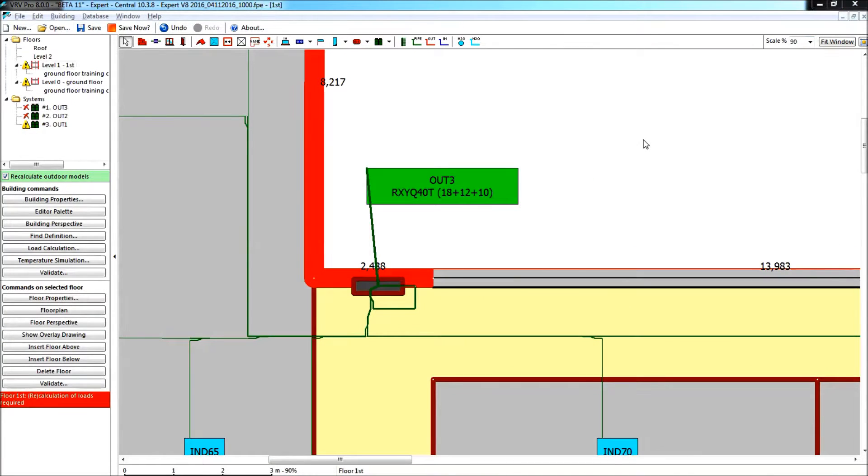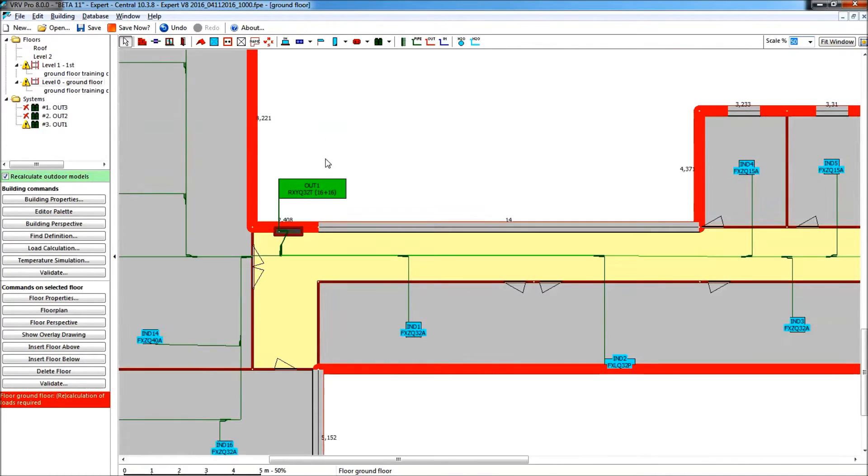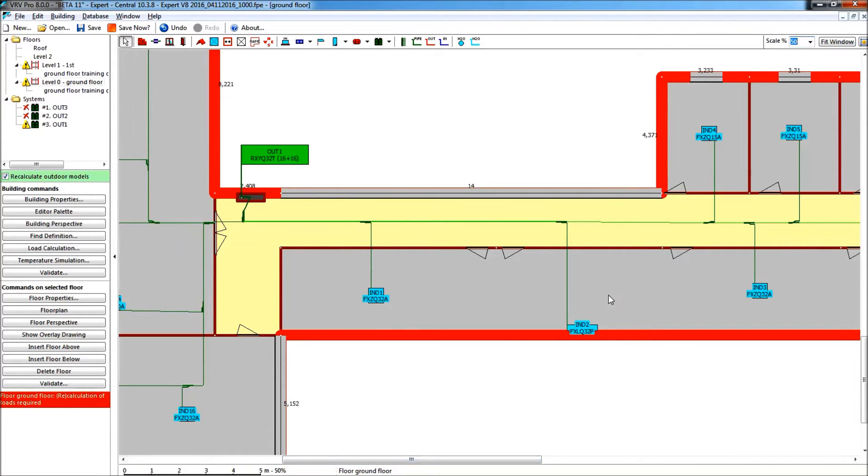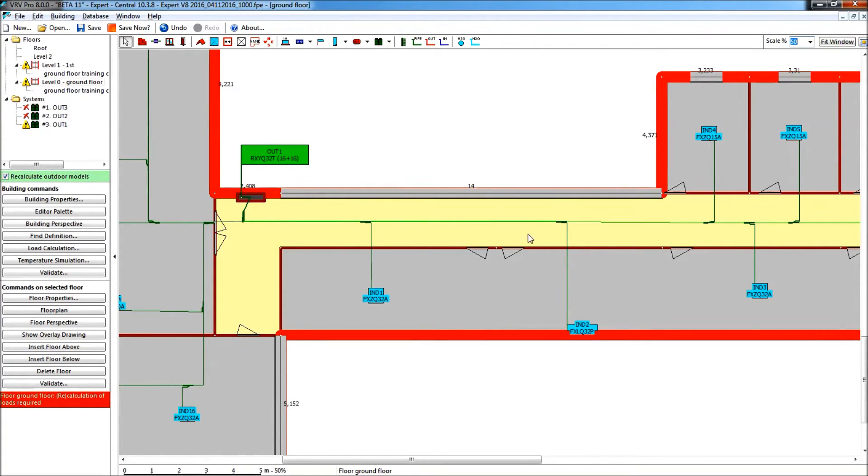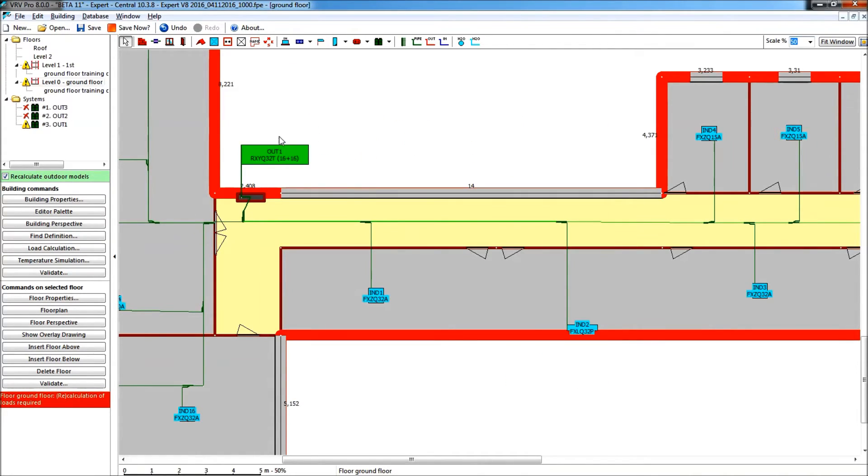There is an aspect that I forgot to mention to you, but just before we leave, I have to go down to level 0 again in the bottom exercise, and remember, we still had those warnings about longest minus shortest piping and so on. We didn't have it in the end, because actually the program did make corrections to upsize the piping, and we're used to having the green piping for 2-pipe and the purple for the 3-pipe, the heat recovery. Now you see we have two tints of green. Actually, if you go to File Options, in the floor plan colors, you see here now, we have 2-pipe is green, and upsized 2-pipe is pale green, and the same for purple. So this is valuable information. We already had this indication of upsized piping in the pipe schematic, but here we have it on the floor plan as well.